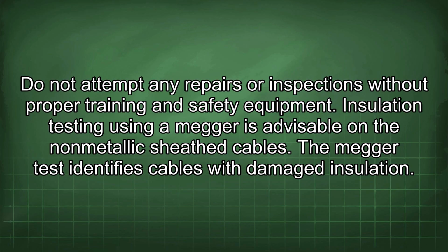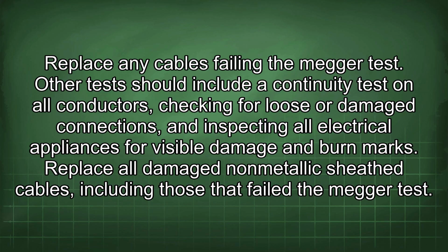Insulation testing using a megger is advisable on the non-metallic sheath cables. The megger test identifies cables with damaged insulation. Replace any cables failing the megger test. Other tests should include a continuity test on all conductors, checking for loose or damaged connections, and inspecting all electrical appliances for visible damage and burn marks.